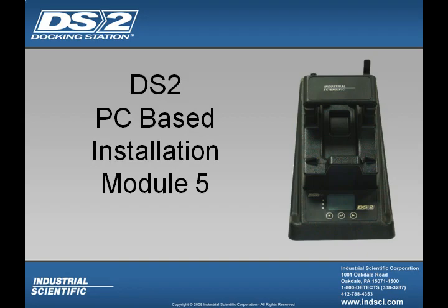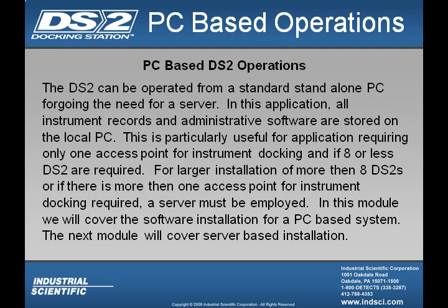Welcome to Module 5. In this module, we're going to cover the DS2 PC Based Installation. The DS2 can be operated from a standard standalone PC, foregoing the need for a server. In this application, all instrument records and administrative software are stored on the local PC.